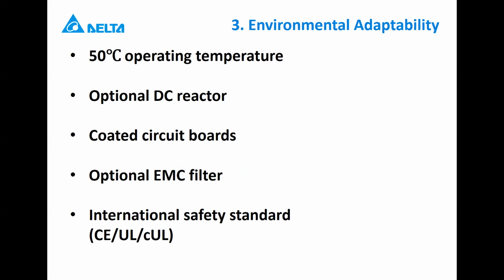For environmental adaptability, our C2000 drives can go up to 50 degrees Celsius operating temperature. For specialized applications, or where you need better harmonics, you can add on a DC reactor or an EMC filter. All our VFD drives have coated circuit boards, so they can be used in harsh environments. We also meet all required international safety standards, like CEUL.